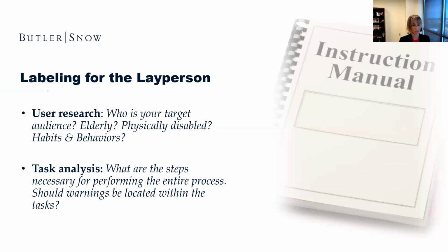And another thing that we can do is look at task analysis. Task analysis involves breaking down a complex activity into smaller, manageable, bite-sized steps. Think about the tasks necessary for performing this process. Would warnings be helpful within the task? By identifying critical steps in device operation, you can uncover where errors are more likely to happen. Then you can craft warnings to address those common mistakes. And task analysis will help you gauge the required skill level for the device operation, which will also allow you to create warnings that cater to both a novice and an experienced user.